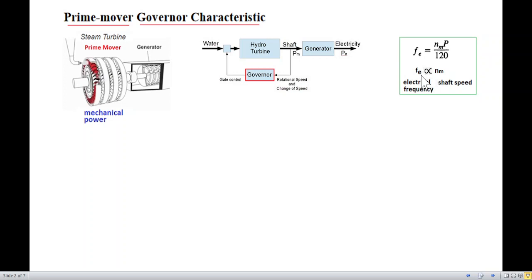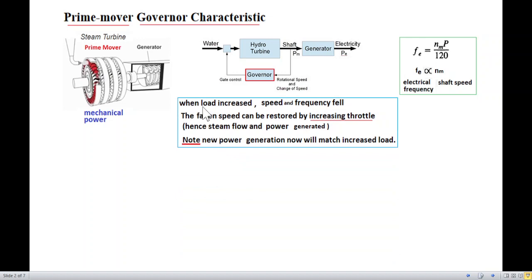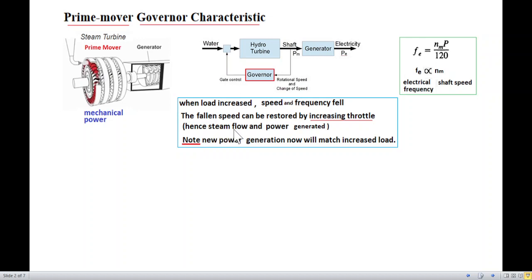The electrical frequency is proportional to the shaft speed. When the load increases, the speed and frequency will fall. The speed can be restored by increasing the throttle — by controlling the flow of water or steam to the turbine — so that steam flow and generated power increase.